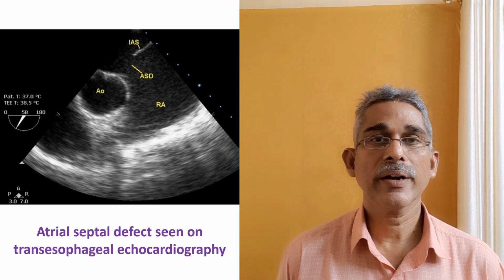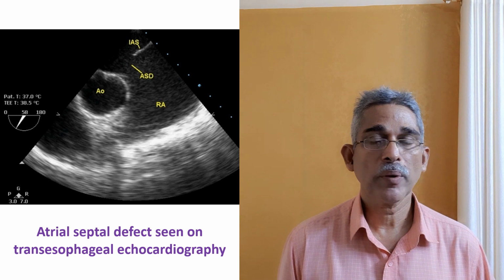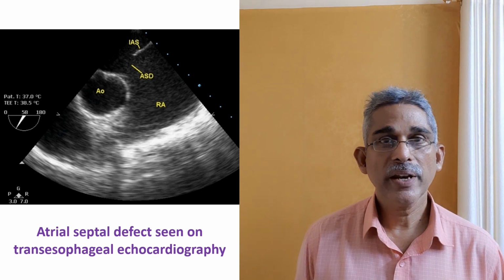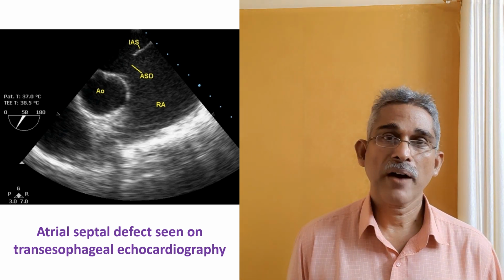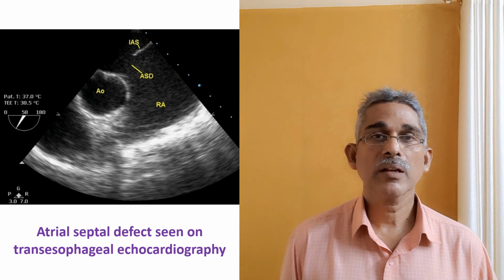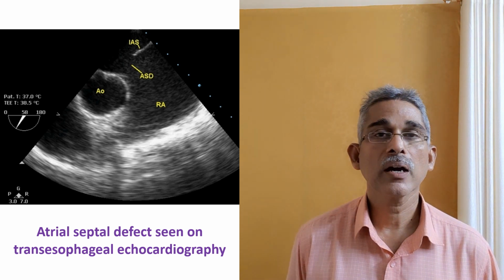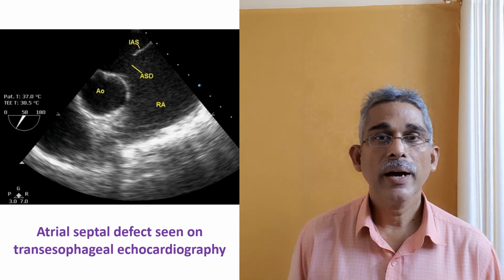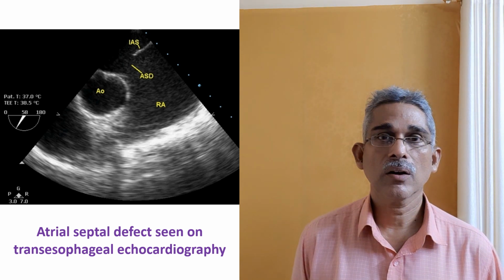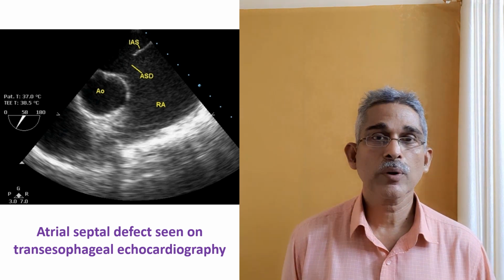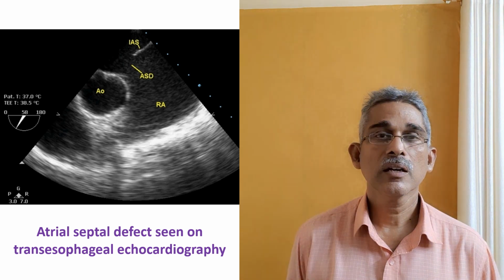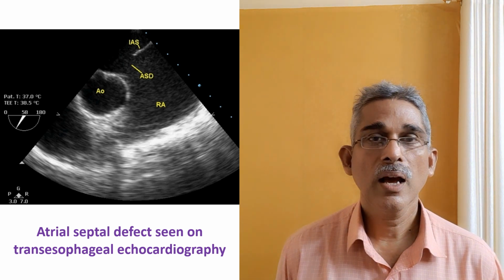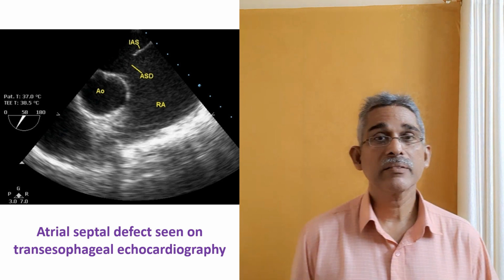In usual adult echocardiography, the probe may be about 2.25 megahertz. Pediatric, you can have 5 megahertz. Neonatal, you may have 7.5 megahertz or 10 megahertz.